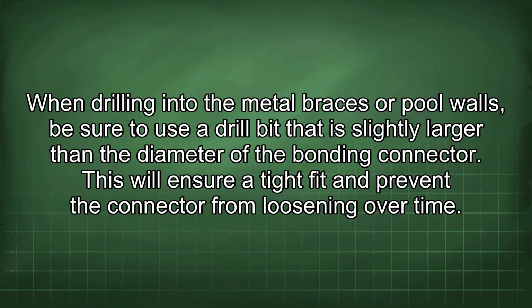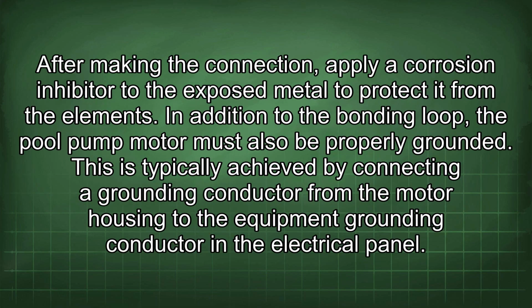When drilling into the metal braces or pool walls, be sure to use a drill bit that is slightly larger than the diameter of the bonding connector. This will ensure a tight fit and prevent the connector from loosening over time. After making the connection, apply corrosion inhibitor to the exposed metal to protect it from the elements.